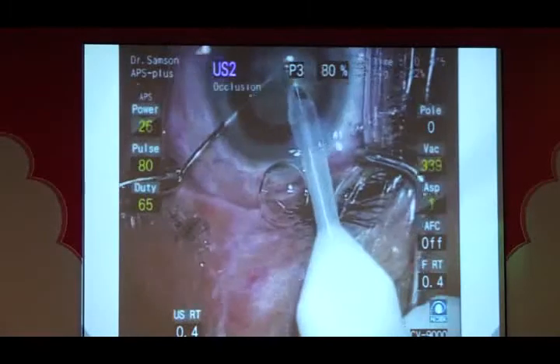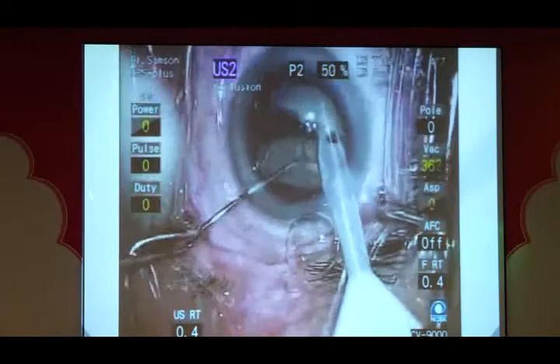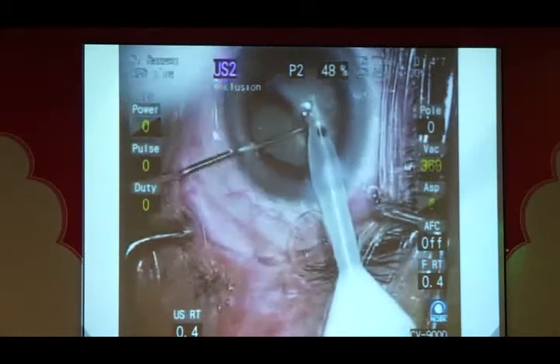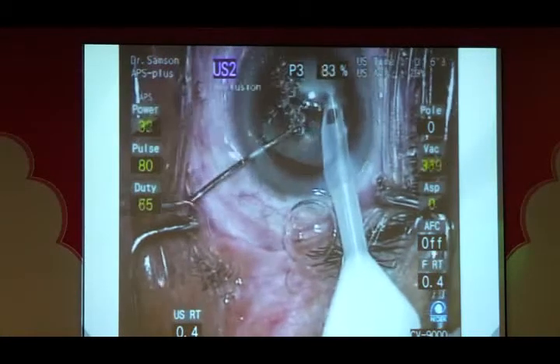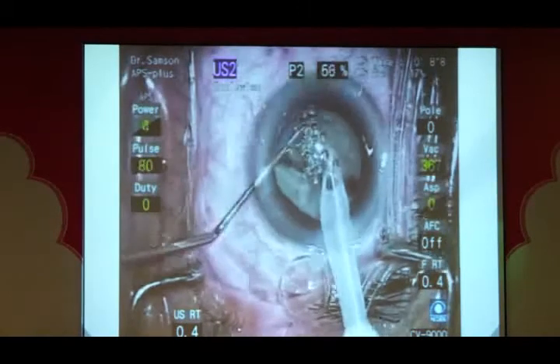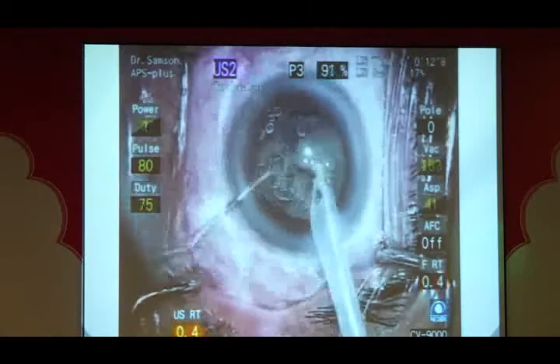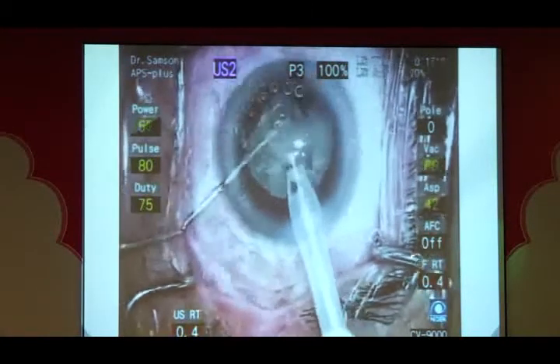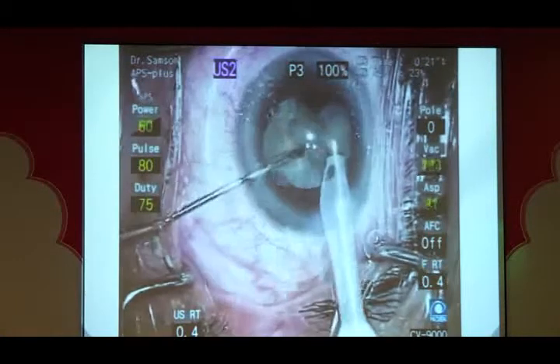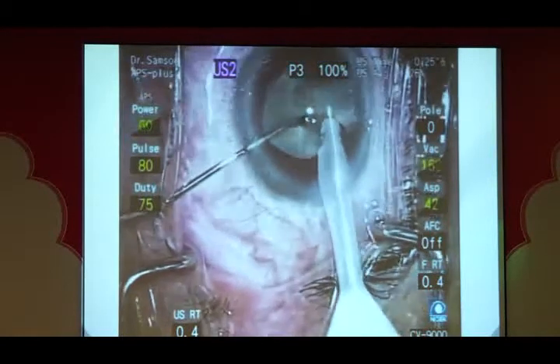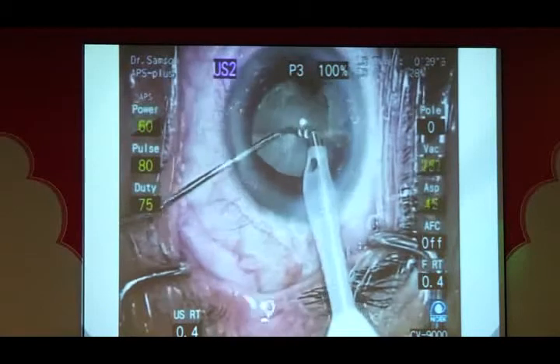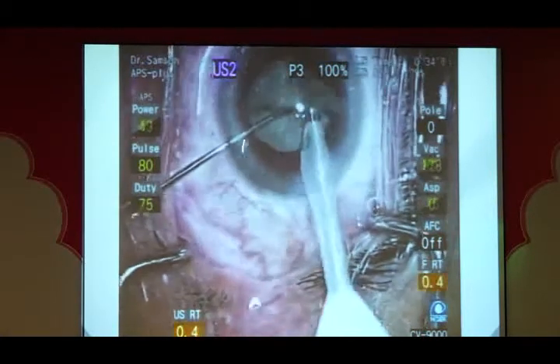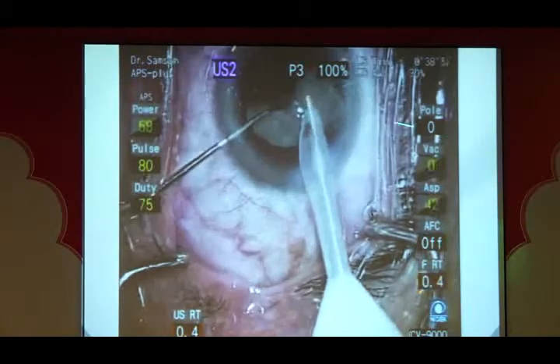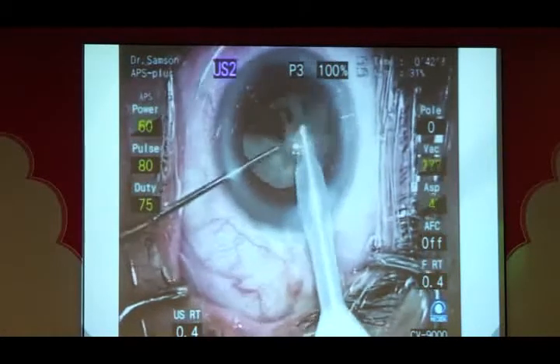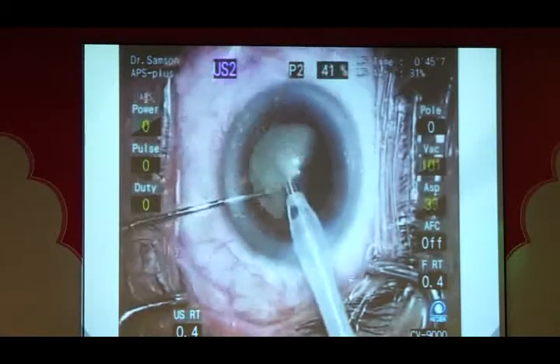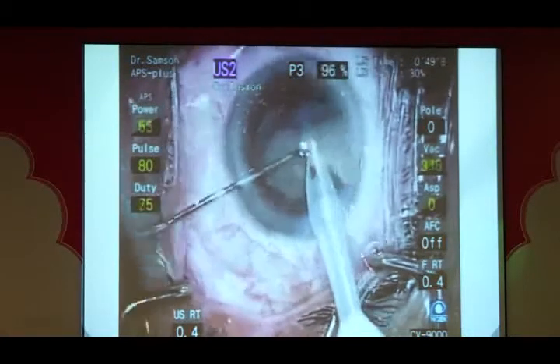Okay, here's probably the first time I use this. Watch what happens and observe this area. When it turns orange, that's when the machine stops. That's post-occlusion. Okay, so I'm actually doing a chop. Notice that? So you're assured that there is no inadvertent surge. It minimizes surge because the machine stops, on top of the irrigation assist bottle. Therefore, you have a very stable chamber no matter how high your vacuum or your aspiration is. I've tried this, my aspiration is 42. I've tried it to the limits of 60, and nothing happens. Post-occlusion surge is nil.